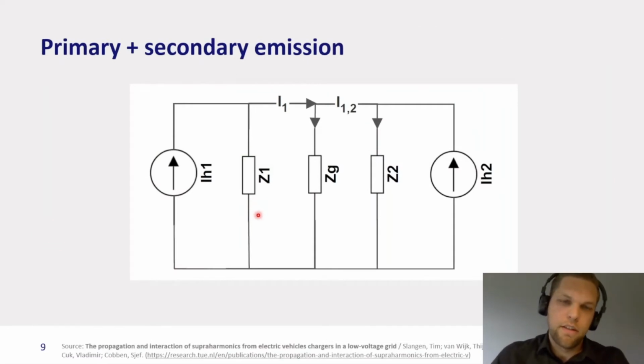Here's a simple schematic showing the difference between primary and secondary emission. Let's say one device is depicted here as a current source, in this case a supraharmonic current source. A supraharmonic current is injected, and part of it is absorbed by its internal impedance, Z1, while part flows out of the device. This is the external emission of device 1, called the primary emission.